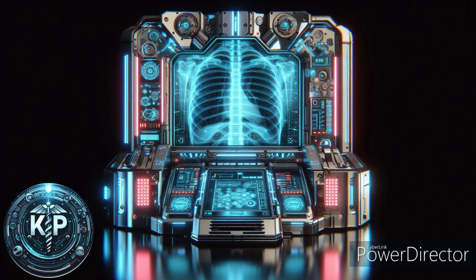X-ray tube issues. Common causes of failure: cathode filament failure, tube arcing, anode failure, glass housing cracks or oil leaks, aging of tube components, rotor bearing failure. Solution, technical approach: use diagnostic tools to assess tube performance. High voltage generator problems. Issue: faults in the high voltage generator impact image quality. Solution, technical approach: regularly inspect and maintain the generator. Address voltage fluctuations using specialized equipment.